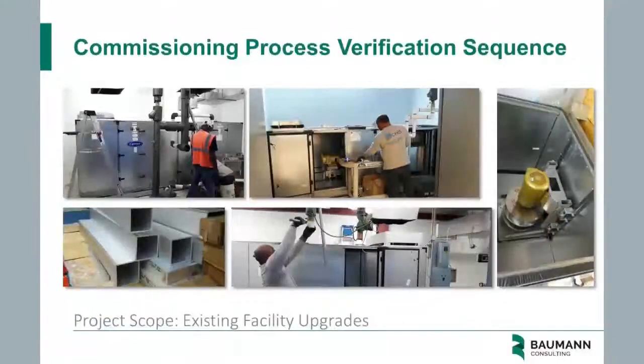Now that the new units have been brought in, they need to be reconnected and all components confirmed and checked out. Most of this equipment came on a ship through three to four weeks of transit, and components could have fallen away or moved during delivery. So it's important to open the entire cabinets, quality check that all components are still attached and secured, and make sure everything came through properly.